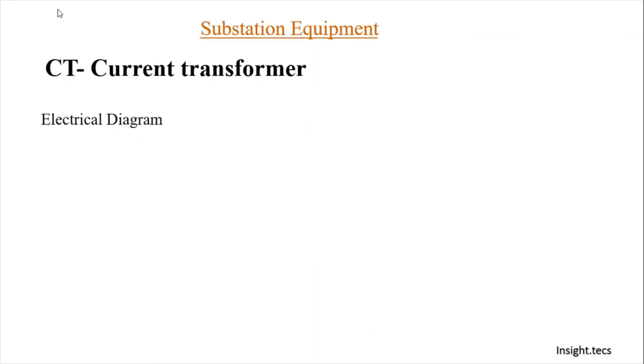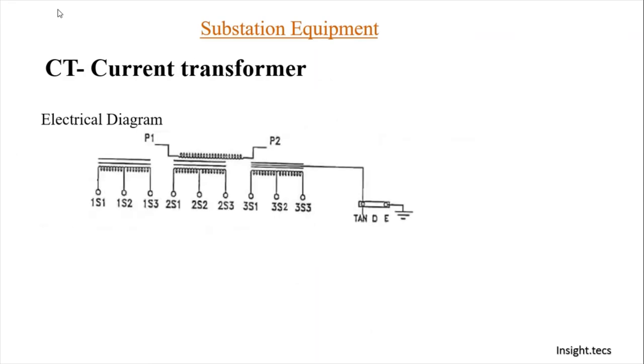Now let us understand the electrical diagram of a current transformer. Shown over here is the electrical diagram of a current transformer. P1 and P2 represent primary winding, and S represents the secondary winding. As you can see over here, the secondary winding is having 3 cores. This is core 1, this is core 2, and this is core 3. Each individual core has 3 tappings: 1, 2, and 3. 1S1 represents the core and this 1 represents its tapping. So 1S1 means it is the first tapping of the first core, 1S2 means it is the second tapping of the first core, and 1S3 means it is the third tapping of core 1. Similarly, it can be understood for core number 2 and core number 3 as well.